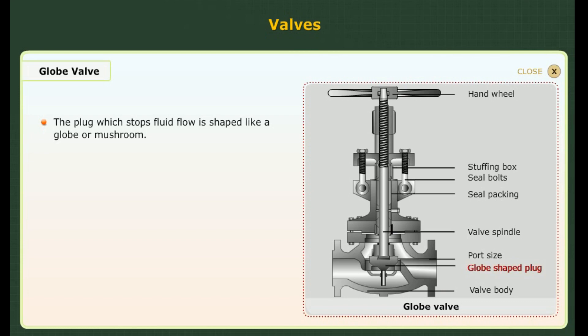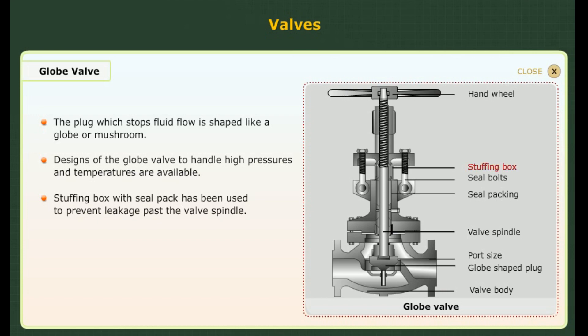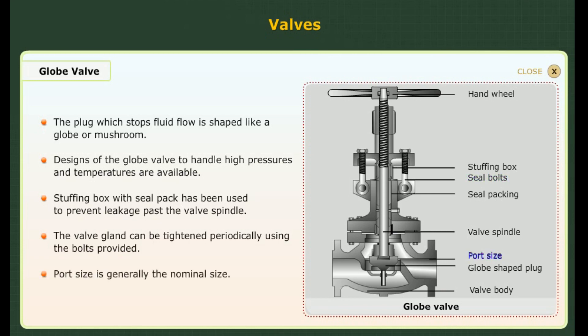Globe valve. The plug which stops fluid flow is shaped like a globe or a mushroom. Designs of the globe valve to handle high pressures and temperatures are available. A stuffing box with seal pack has been used to prevent leakage past the valve spindle. The valve gland can be tightened periodically using the bolts provided. Port size is generally nominal size. Port fitting could be either flanged as shown, or screwed fitting where the body is with threads.